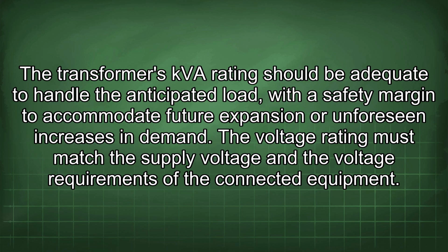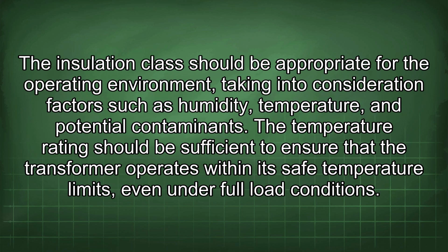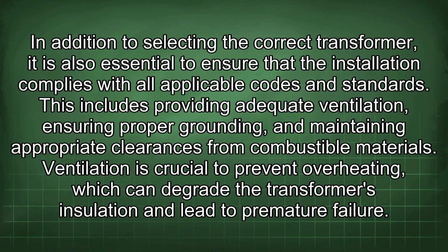The voltage rating must match the supply voltage and the voltage requirements of the connected equipment. The insulation class should be appropriate for the operating environment, taking into consideration factors such as humidity, temperature, and potential contaminants. The temperature rating should be sufficient to ensure that the transformer operates within its safe temperature limits, even under full load conditions. In addition to selecting the correct transformer, it is also essential to ensure that the installation complies with all applicable codes and standards.